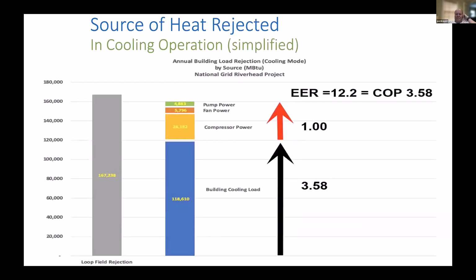Now looking at cooling, the opposite is the case. Cooling load was only 118,000 MBTUs, but there were 167,000 rejected into the loop field, because we also now have to reject the compressor power, the power of the pumps, and the power of the fans. That all otherwise would end up as heat in the building. In this case, it needs to be also rejected into the loop field.